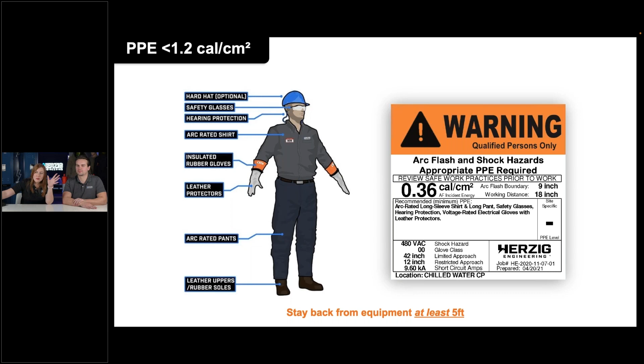Then we've got maybe a coverall, or they still have a uniform, it could be arc rated, got the gloves, and now you add in the face shield, maybe a balaclava as well. This is where I'd say stay back at least 10 feet for unqualified persons. Hopefully, and you can see on the arc flash label 50 inches for arc flash boundary, and of course the limited approach boundary for 480 volts.